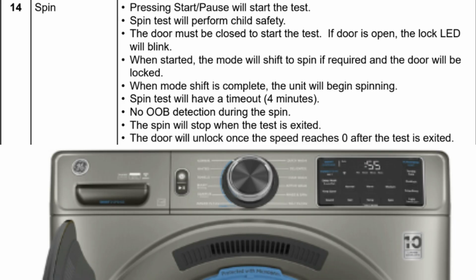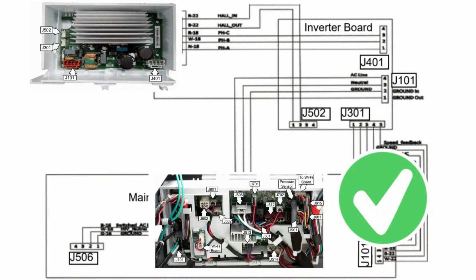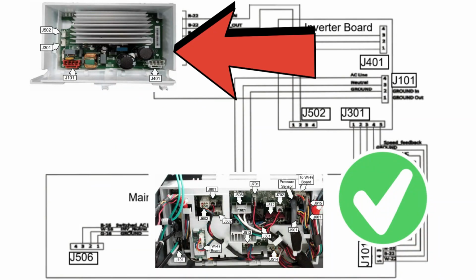If you have 120 volts at the main board and at the inverter, and your motor windings are all evenly reading around 14.2 ohms, then your motor is good. If the motor is not physically locked and there is still no feedback signal from the hall sensor, the inverter board is almost certainly defective. Again, in my experience, about 99% of the time with this issue, it's the inverter board.